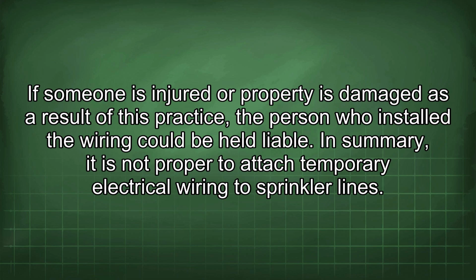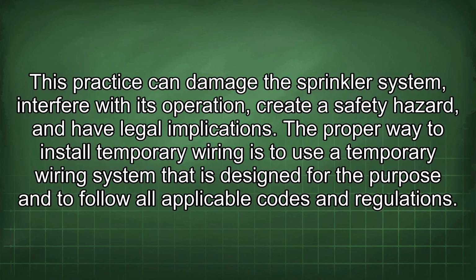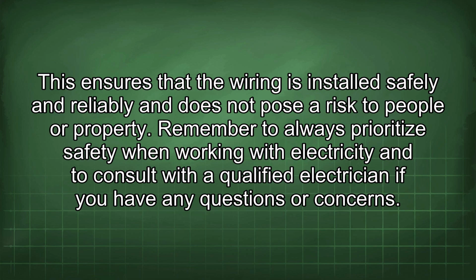In summary, it is not proper to attach temporary electrical wiring to sprinkler lines. This practice can damage the sprinkler system, interfere with its operation, create a safety hazard, and have legal implications. The proper way to install temporary wiring is to use a temporary wiring system that is designed for the purpose and to follow all applicable codes and regulations. This ensures that the wiring is installed safely and reliably and does not pose a risk to people or property.